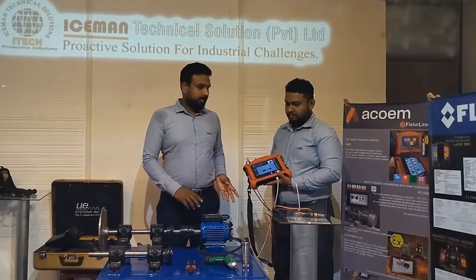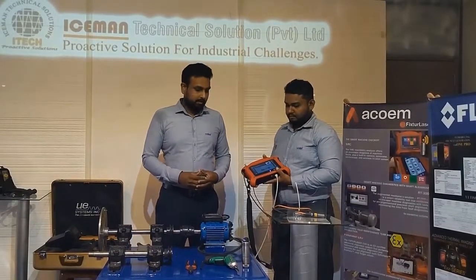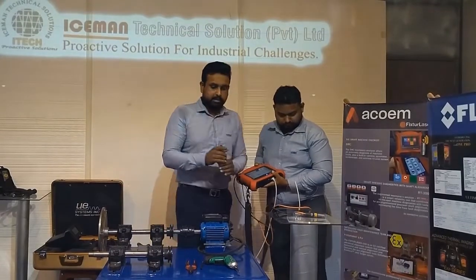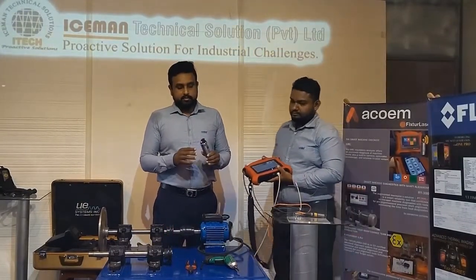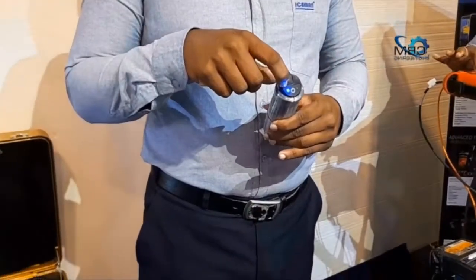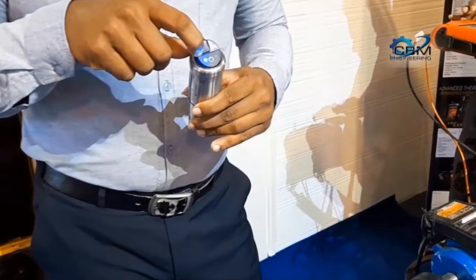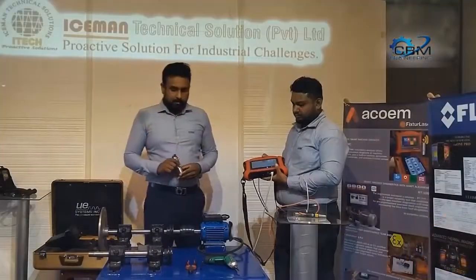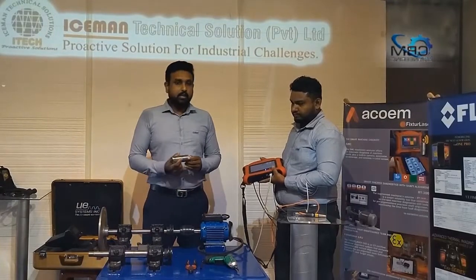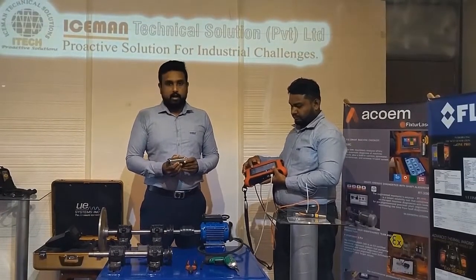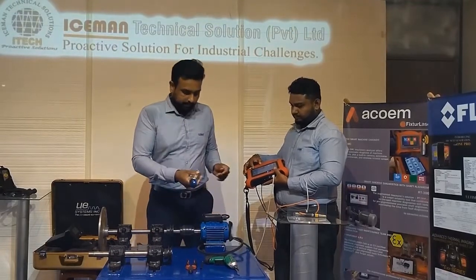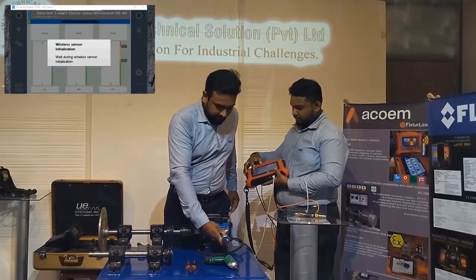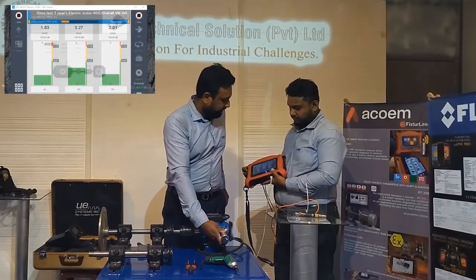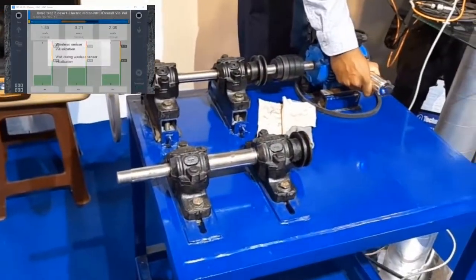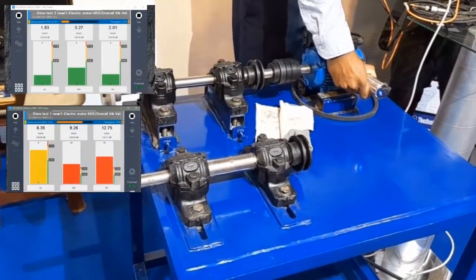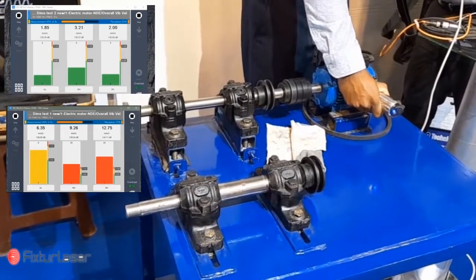So we will check how the vibration values come out after the balancing. We take the vibration triaxial sensor. This is connected by Bluetooth. The Bluetooth connection is given an OK mark by this blue color light. After the running condition, we check the vibration value after the balancing. First we take the vibration on motor one drive. You can see the vibration display. The color is green. That means good condition.